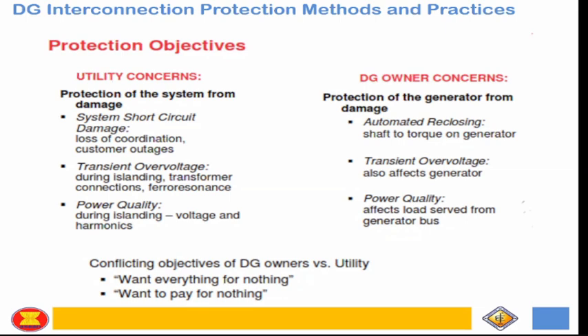And worst case, you know that the fault current is higher, the out-of-synchronism fault. So there's a potential risk on the breaker. The breaker might even explode if it exceeds the interrupting capacity of your recloser. So those are the potential risks.